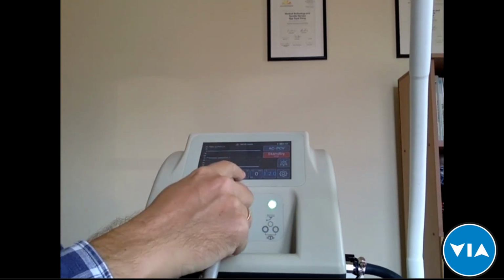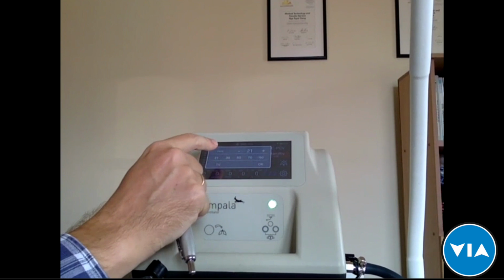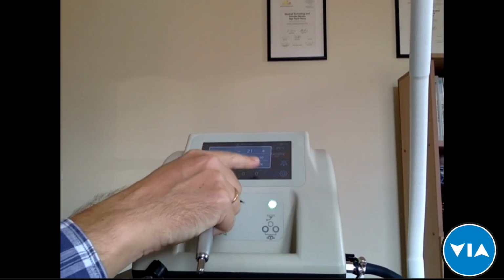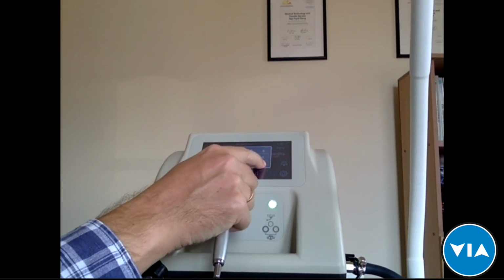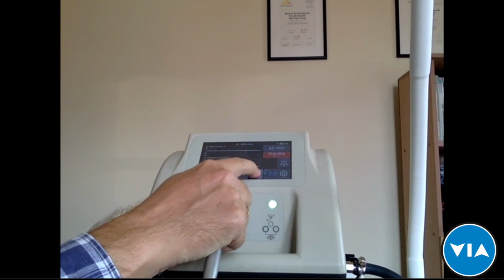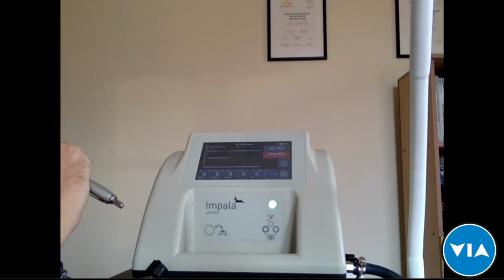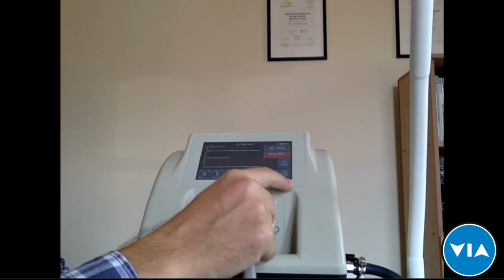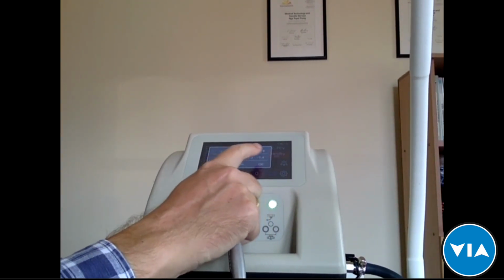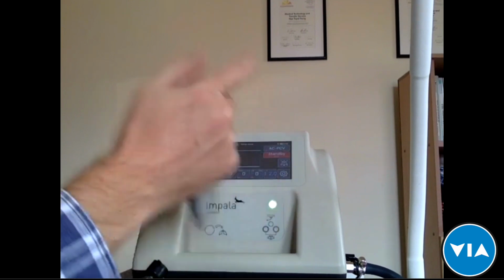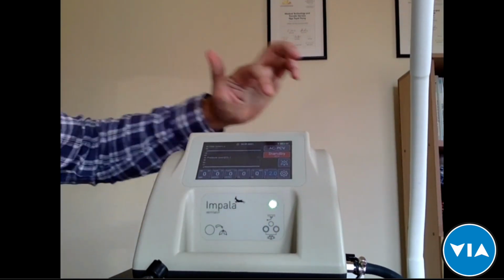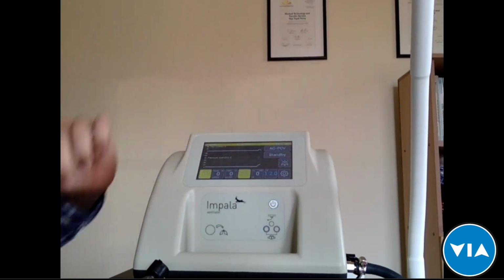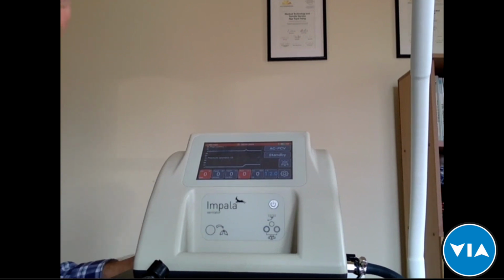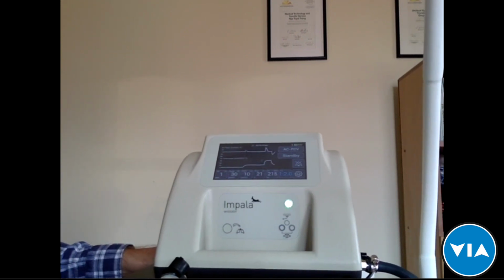And flow, sorry, this is FiO2. So we can choose the oxygen level. I leave it at 21. And volume we cannot select in this mode because this is pressure control mode. And there is an IE ratio as well here. So we choose this one. Then when we're ready, we just press the standby button and the device starts operating.